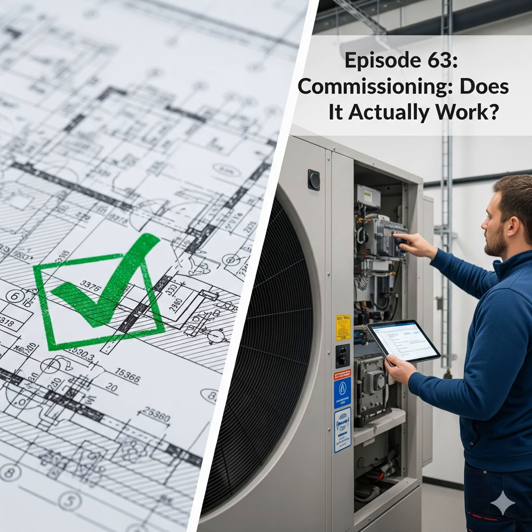They participate in design reviews, flagging potential conflicts between systems, ensuring that everything from the window glazing specified to the fan coils chosen is not just architecturally pleasing, but functionally sound, verifiable, and optimized for the performance goals in the OPR. So they're checking performance specs too, like R values? Absolutely, reviewing R values, solar heat gain coefficients for windows, coefficient of performance for chillers, and the specific control logic for variable air volume VAV boxes, all the details that dictate actual performance.